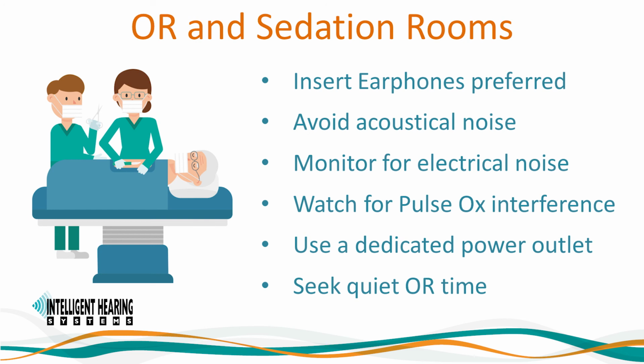ORs are also electrically noisy. The use of diathermy machines in adjacent ORs can be problematic. Autoclaves and microwave ovens also radiate interference, as do hospital pager systems, elevators, escalators, air conditioning systems, etc. Mobile phones should be turned off during testing. Pulse oximeters are sometimes a source of electrical interference. Try turning it off to see if this eliminates the interference.